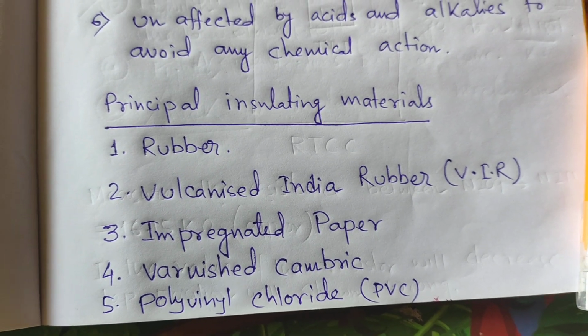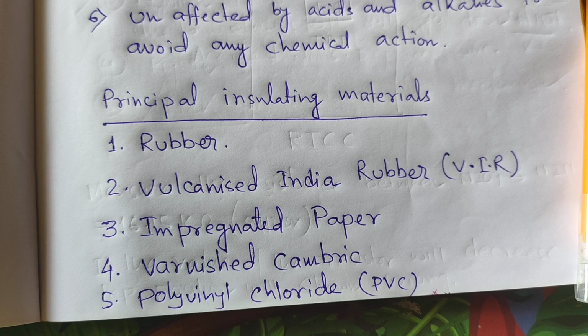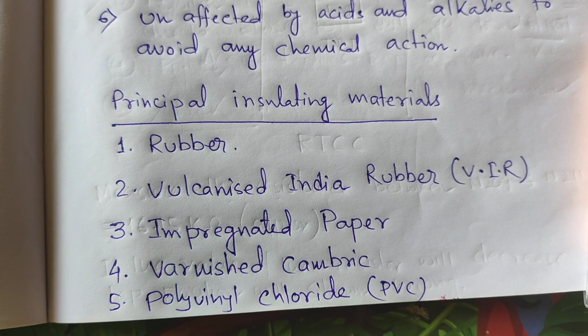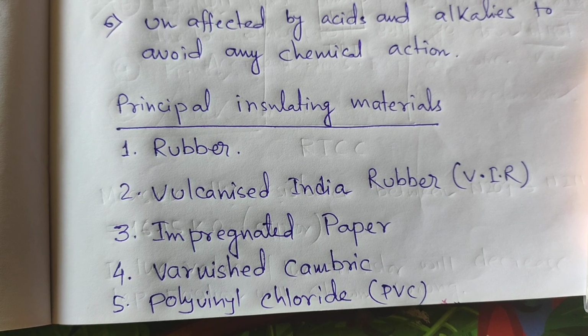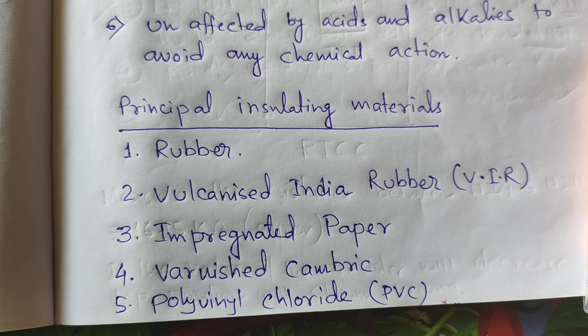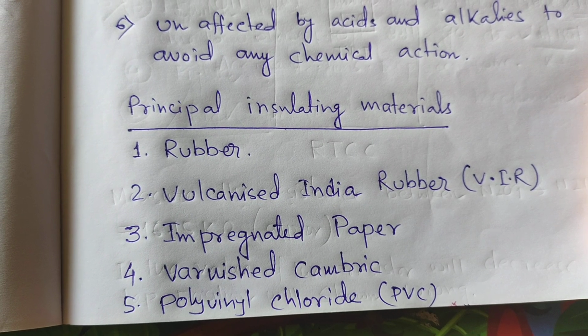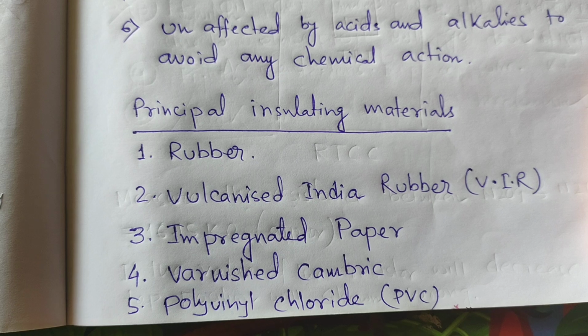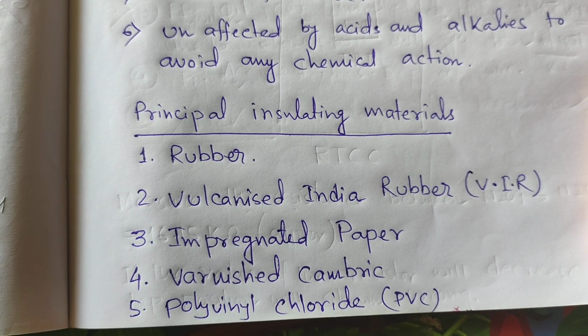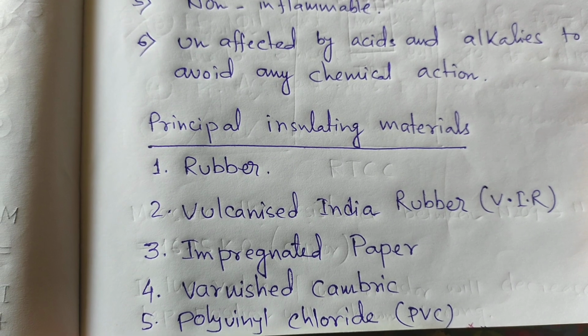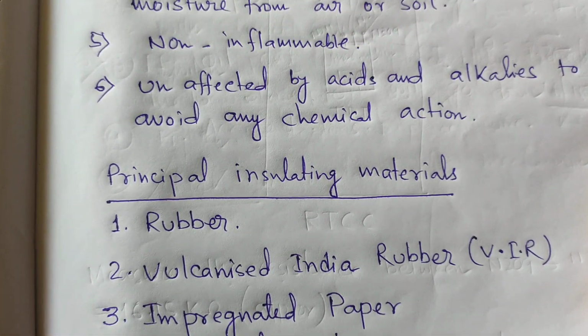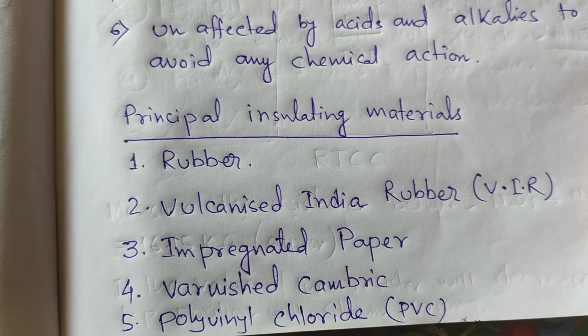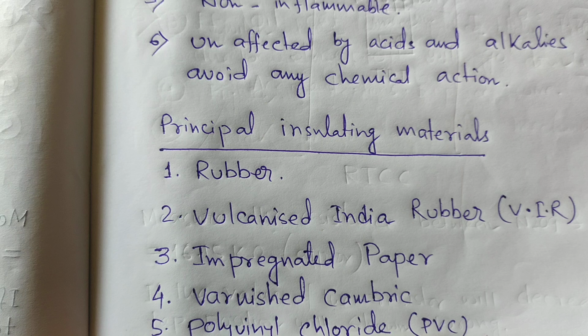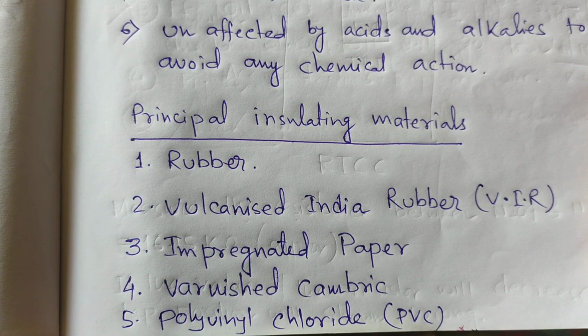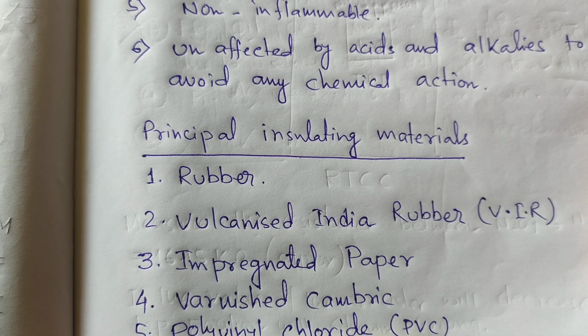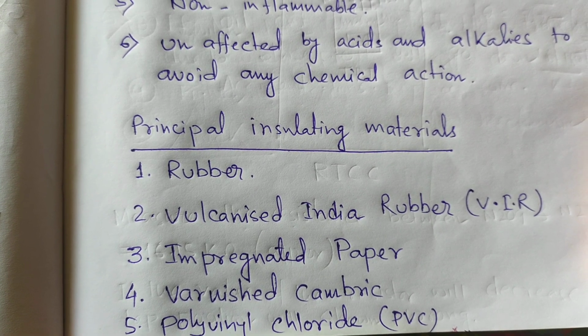Impregnated paper consists of chemically pulped paper made from wood chippings and impregnated with some compounds such as paraffinic and naphthenic material. These types of insulation have almost superseded rubber insulation. Its advantages are low cost, low capacitance, high dielectric strength and high insulation resistance. The only disadvantage is that it is hygroscopic and absorbs moisture, thus lowering the insulation resistance of the cable.